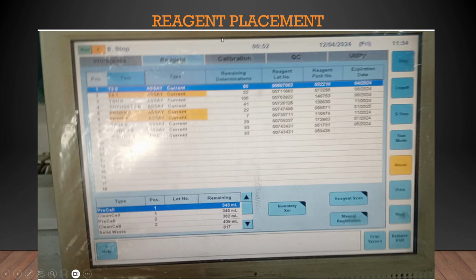Okay, so once that is done, the instrument will be in standby. You can give a reagent scan. Normally in our setup we don't give a reagent scan, we directly go to start, because every time the instrument starts from standby, it always cross checks the reagents, it cross checks the pro cell, clean cell, the cups and tips, everything it cross checks when it comes from standby. Okay, for that purpose we don't give a reagent scan. There are some other small technical reasons why we don't give a reagent scan, but the company always recommends that when you are starting the instrument from standby, you should always give a reagent scan.